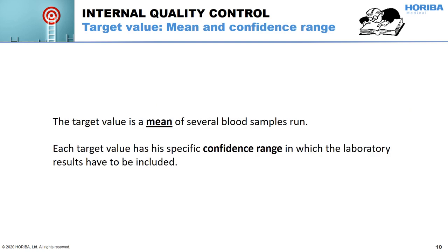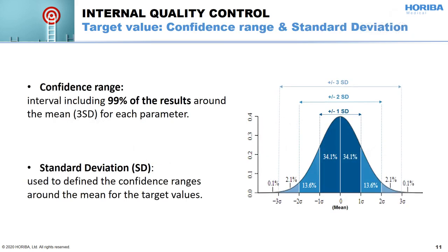The target value is simply a mean of several control sample runs. As we cannot expect the laboratory to exactly reach the target values, the results have to be inside a certain closeness to the target value. This closeness around the mean corresponds to the confidence range, which should statistically include 99% of the results and corresponds to 3 standard deviations, or ±3 SD. ±2 SD includes 95% of the results, and ±1 SD includes only 68% of the results.